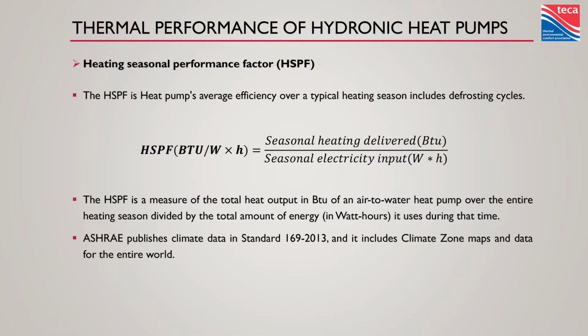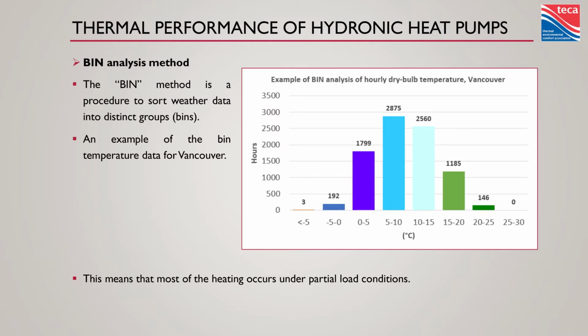It's also a good point to figure out if you do need to change a balancing valve or change a pump speed or something like that. Something about air source heat pumps that I hear a lot of people talk about is, oh, they suck in the winter. They just don't do a good job. A lot of people, especially in the forced air industry, use gas or electric as a backup, and when that comes in, in a lot of cases, the heat pump turns off completely. It no longer has enough capacity to heat the house, so off it goes, on comes the backup, and up goes the hydro bill. So what's nice about hydronics is we can use them in conjunction.